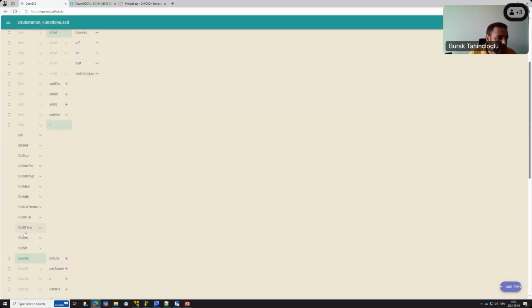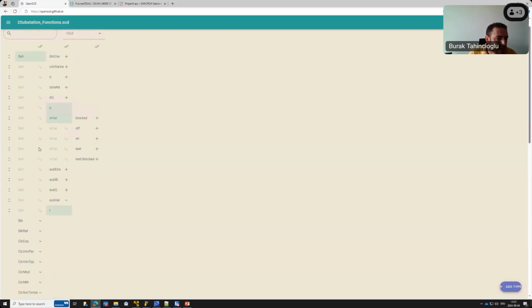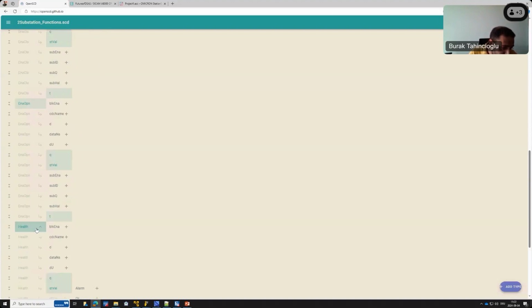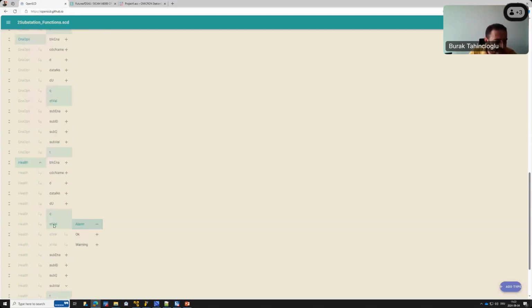For instance, for CILO, maybe I want health as well — it's not mandatory, but I'd like to have it. Under health, you'd expect the status value Q and T, but maybe also a description, D. You can add that. Under the status value, you would normally have three different status data attributes — under the data attribute can be alarm, okay, and warning. If you select all, you get all these possibilities; if you only select alarm and warning, or alarm and okay, your IED can only have those two statuses, nothing else.